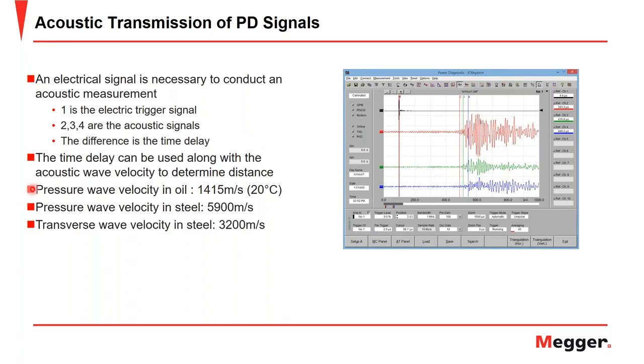So for instance, here we have pressure wave velocities in oil and in steel, as well as a transverse wave velocity in steel. And these wave velocities can be used along with the time delay. So when you have meters per second and then the time delay in seconds, you can cancel that out and just get the meters. That gives you the idea of the location of the partial discharge activity. One thing to note here is that the sensor should be placed as close as possible to the PD source location, and this greatly improves the precision in locating the PD activity.